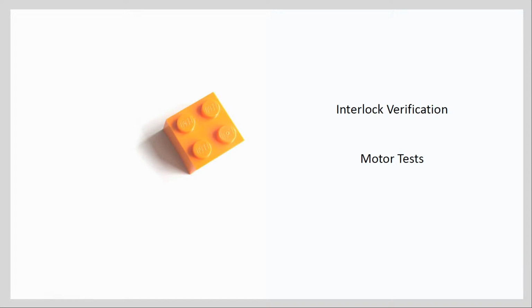That's good. So another important system check to do before any energization is interlock verification. Electrical systems are often designed with interlocks to prevent the system from entering an unsafe operating scenario that could damage equipment or cause harm to people working in the area.